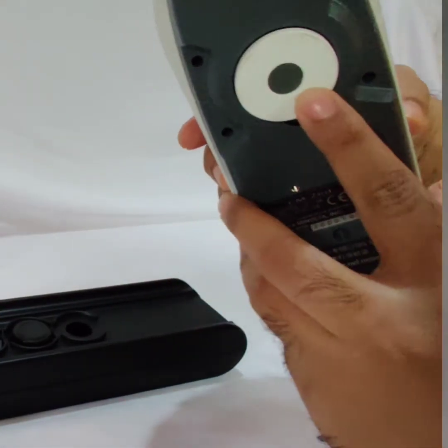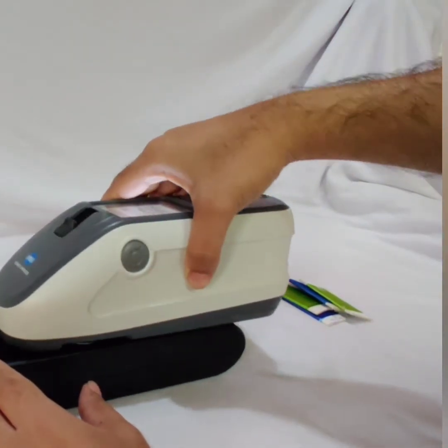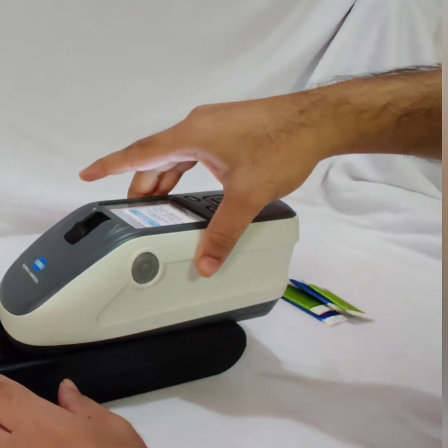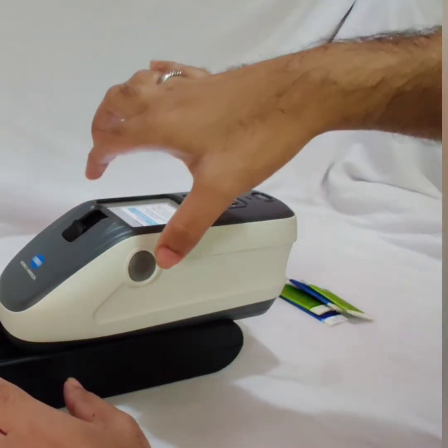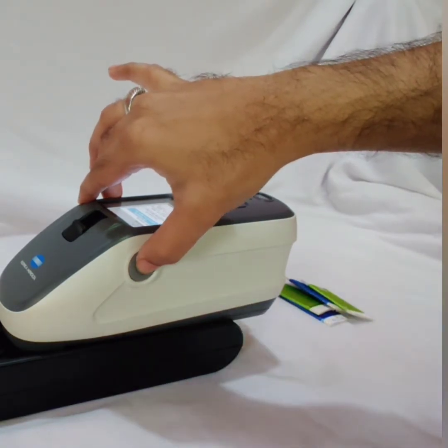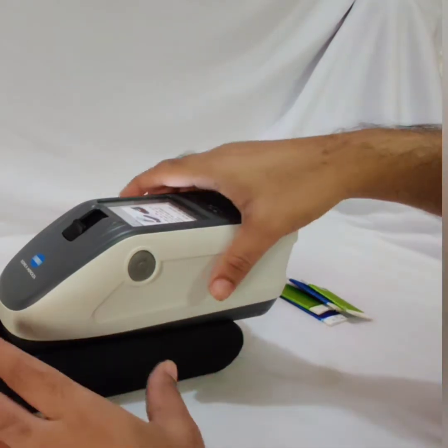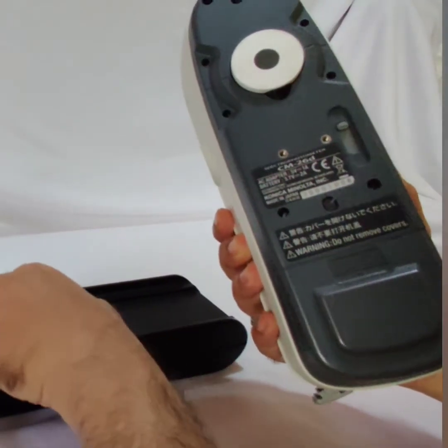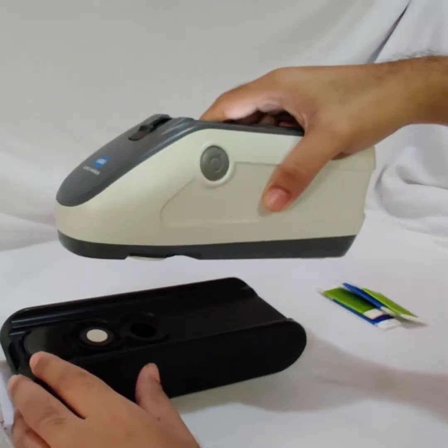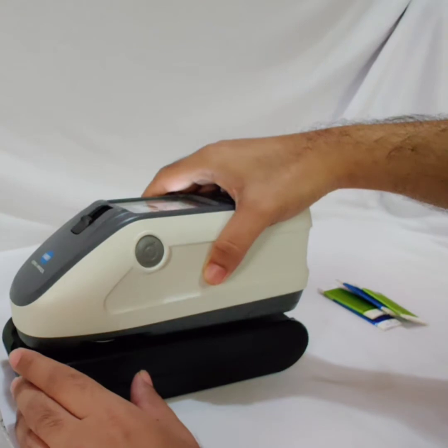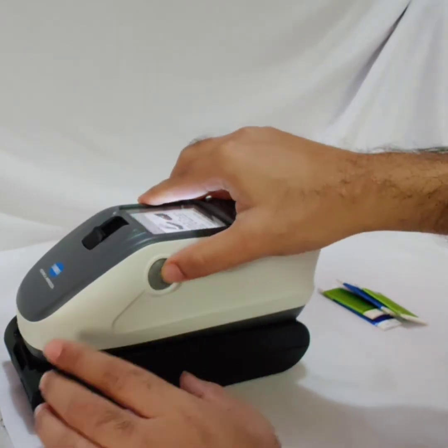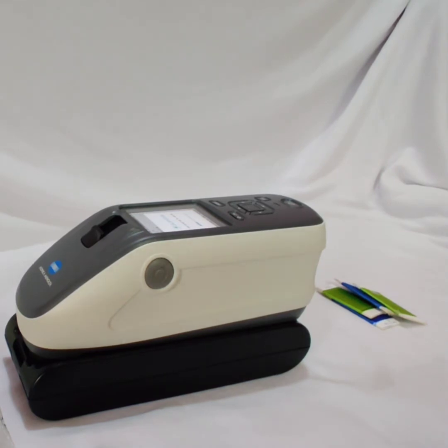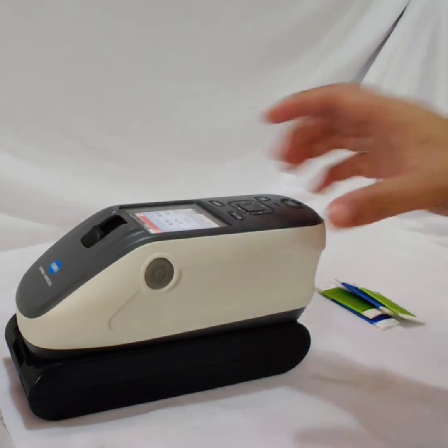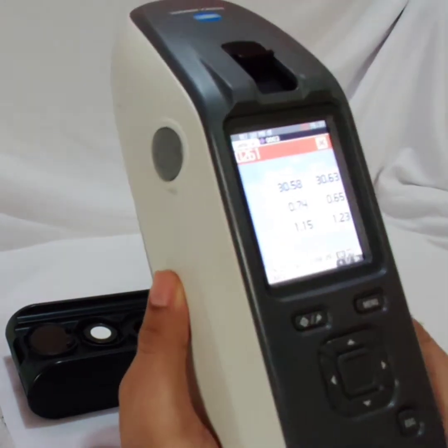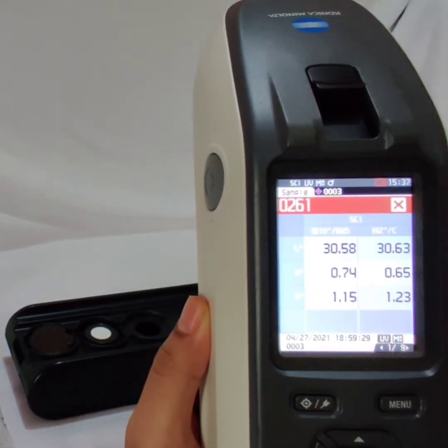I'll put the aperture position on the zero calibration slot. Now it is placed accurately. I will press this button, this one. Now I'll go for white calibration. Same procedure, I'll keep it on the white plate slot and I'll press this button. You can hear the sound of calibration. Here the value shows like this. These are the LAB values.